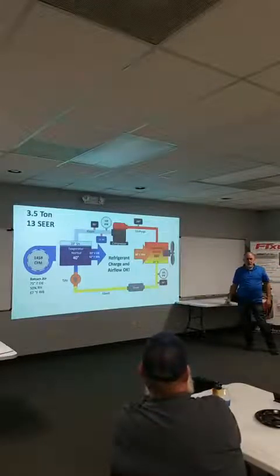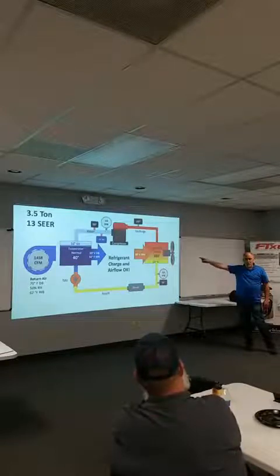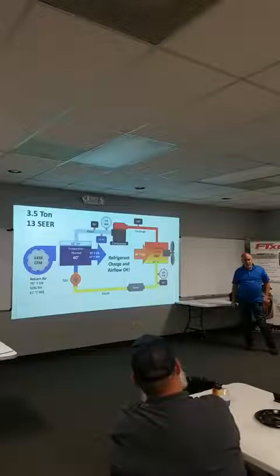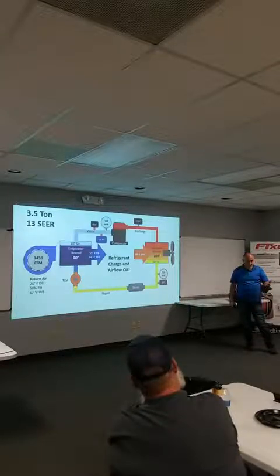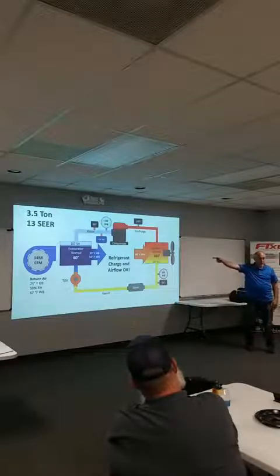It's cold outside, all the refrigerant migrates into the condenser, you gotta start it up, and you don't have anything for your evaporator, and it tanks, right? In the summertime, it's cooler indoors than it is outside, and all your refrigerant migrates into the evaporator where you want it. And the system will start up and run really quick, it'll get up to operating temp.